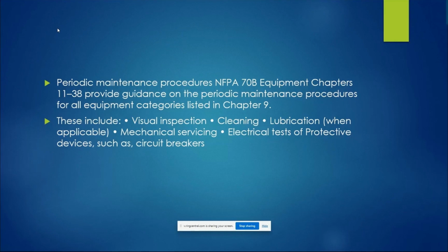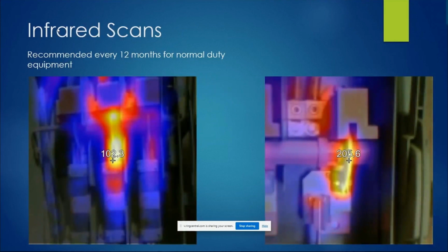Cleaning, we're going to explain to you some rules about that, what cleaning looks like. Lubrication only applies to moving components such as disconnect stabs. There are open air breakers and some other breakers and feeders and motor control centers that have moving components inside that need to be inspected within a 5-year interval at maximum. Then mechanical, and the last part of it is electrical tests of protective devices like circuit breakers, and we'll touch on that one a little bit too.